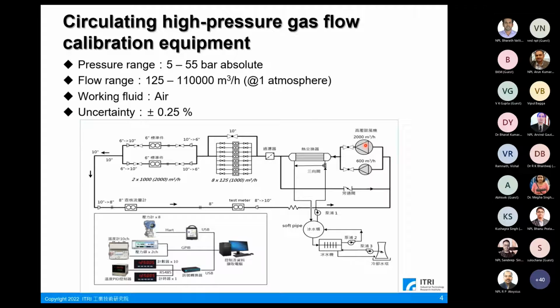Because the high-pressure blower is a heat source, a heat exchanger is used to maintain the fluid at a constant temperature close to the atmospheric temperature. At the maximum actual volume flow rate and working pressure, the fluid temperature does not change by more than 0.2 degrees Celsius within 5 minutes. The maximum uncertainty should not exceed 0.25%. The standard components used in this equipment are 2-inch rotary meters and two 6-inch ultrasonic flow meters, and one 8-inch ultrasonic flow meter is used as a check standard.